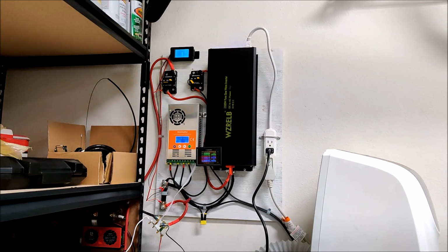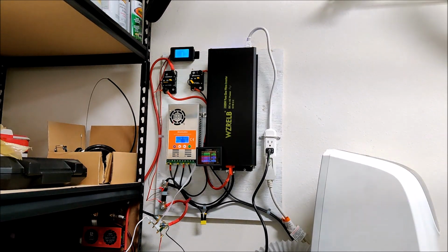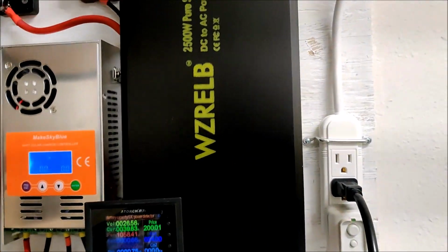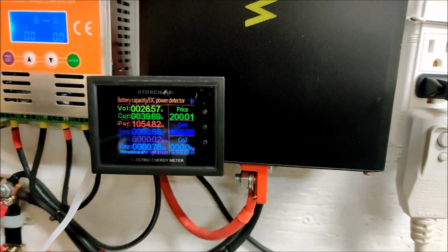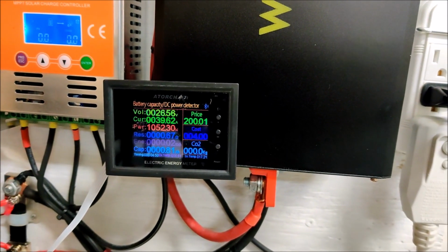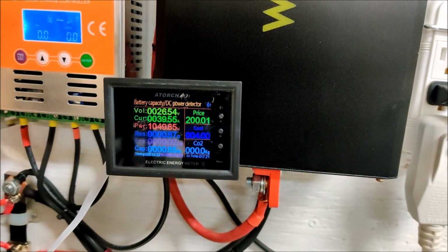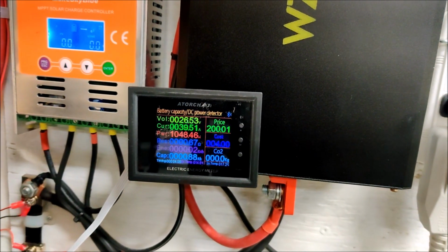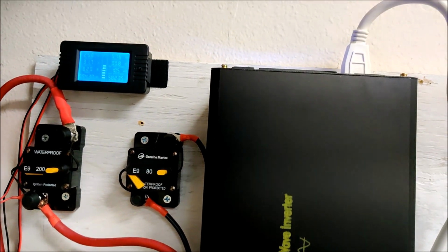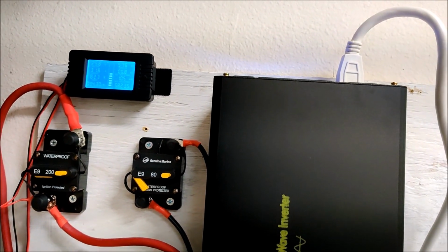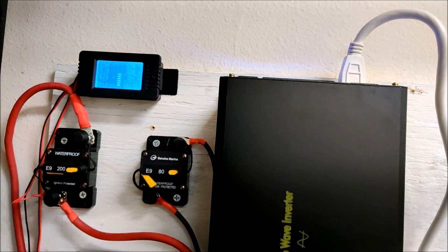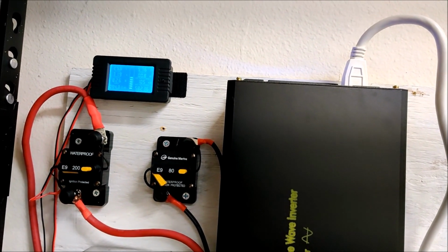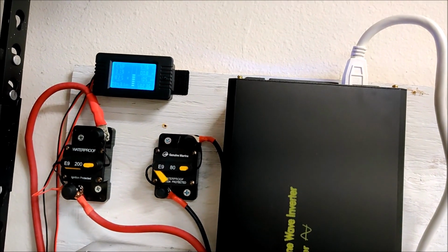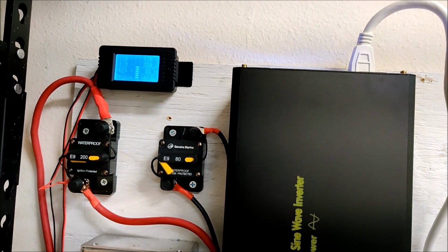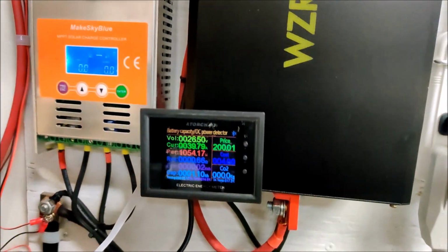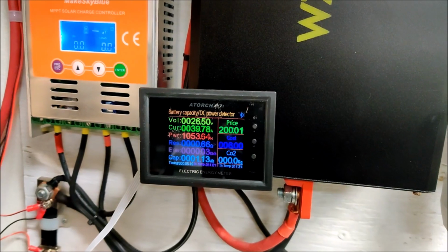So let's compare these meters. This meter is saying that we are pulling 39 amps. We are not - we're pulling about 33, 34 amps. My meter is saying 32 amps, and like I said, this meter is about an amp low at this draw. I've put a clamp meter on it, and we're pulling about 33 amps on this setting. This meter is saying 39 amps. That is a huge difference.